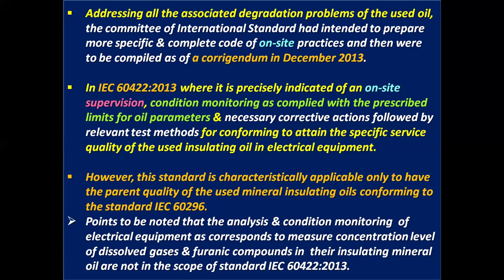Points to be noted: the analysis and condition monitoring of electrical equipment, as corresponds to measuring the concentration level of dissolved gases and furanic compounds in their insulating mineral oils, are not in the scope of standard IEC 60422 2013.